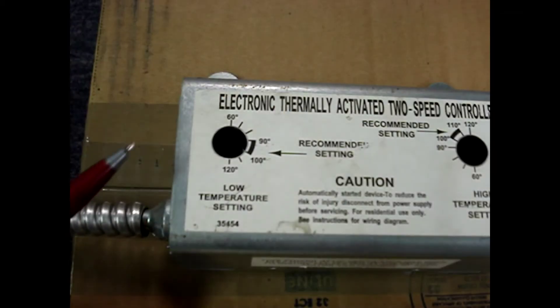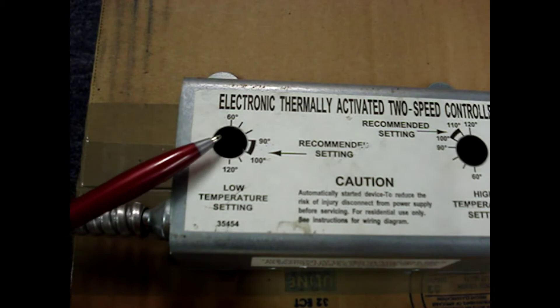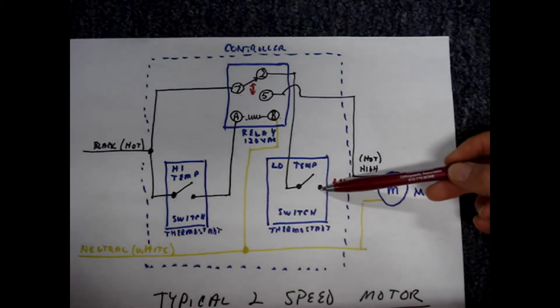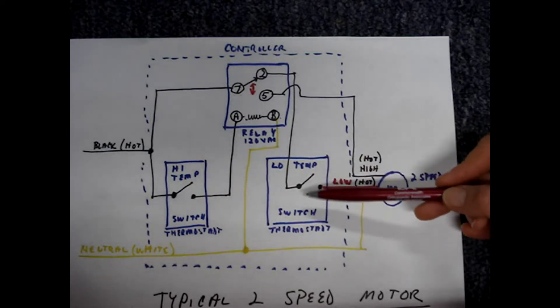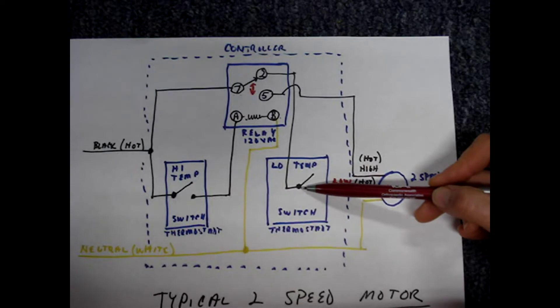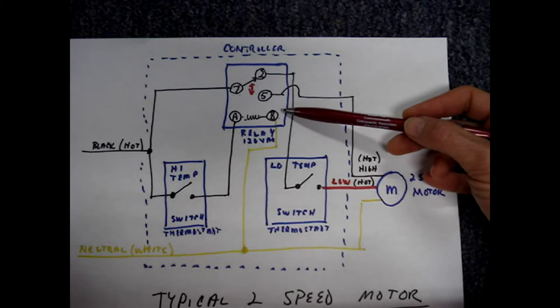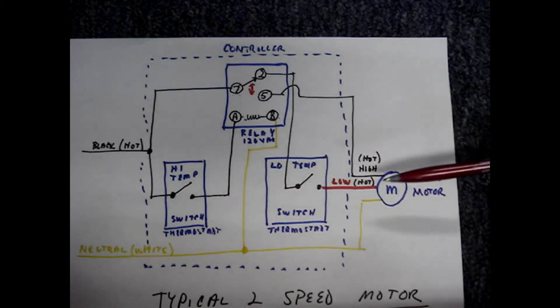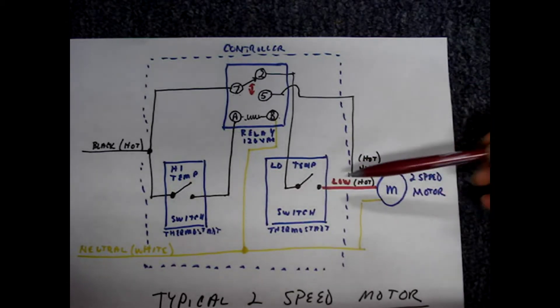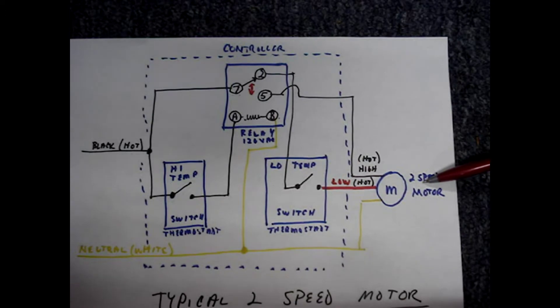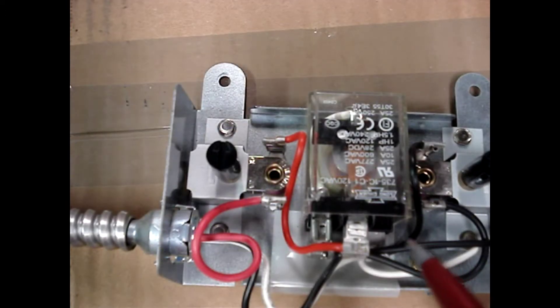When the attic temperature reaches the recommended low temperature setting of 90 to 100 degrees, the low temperature switch closes. And if you remember, the hot was sitting on one side of the low temperature switch when this 120 volt relay was not energized. The hot passes through the switch and onto the low speed winding of the two-speed fan motor.